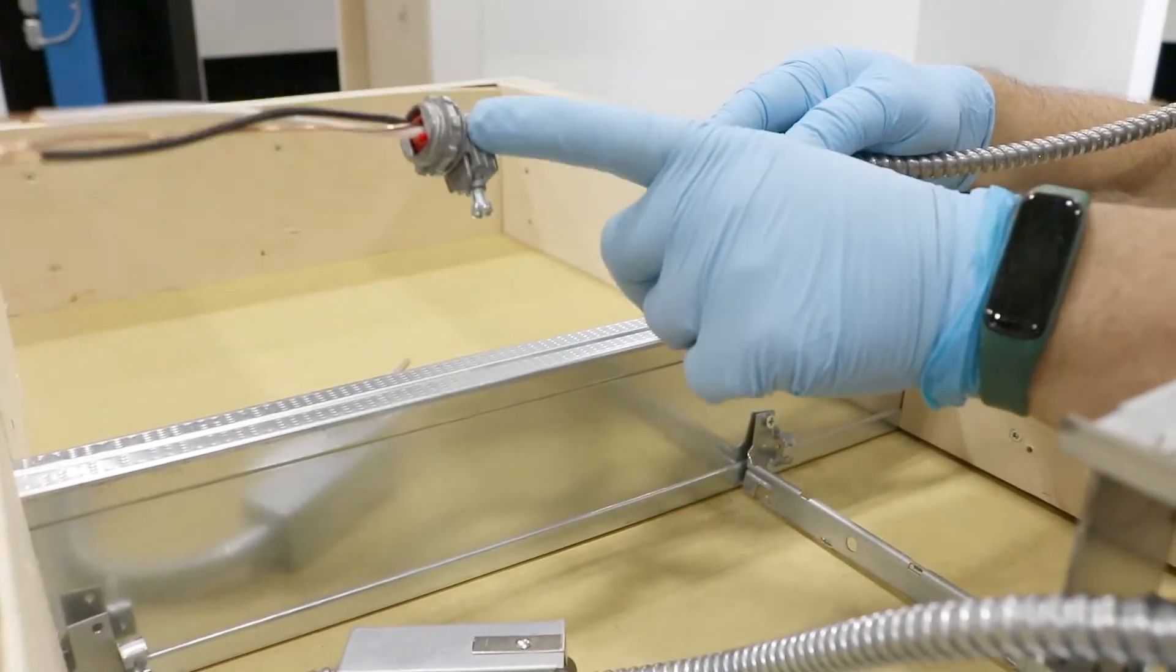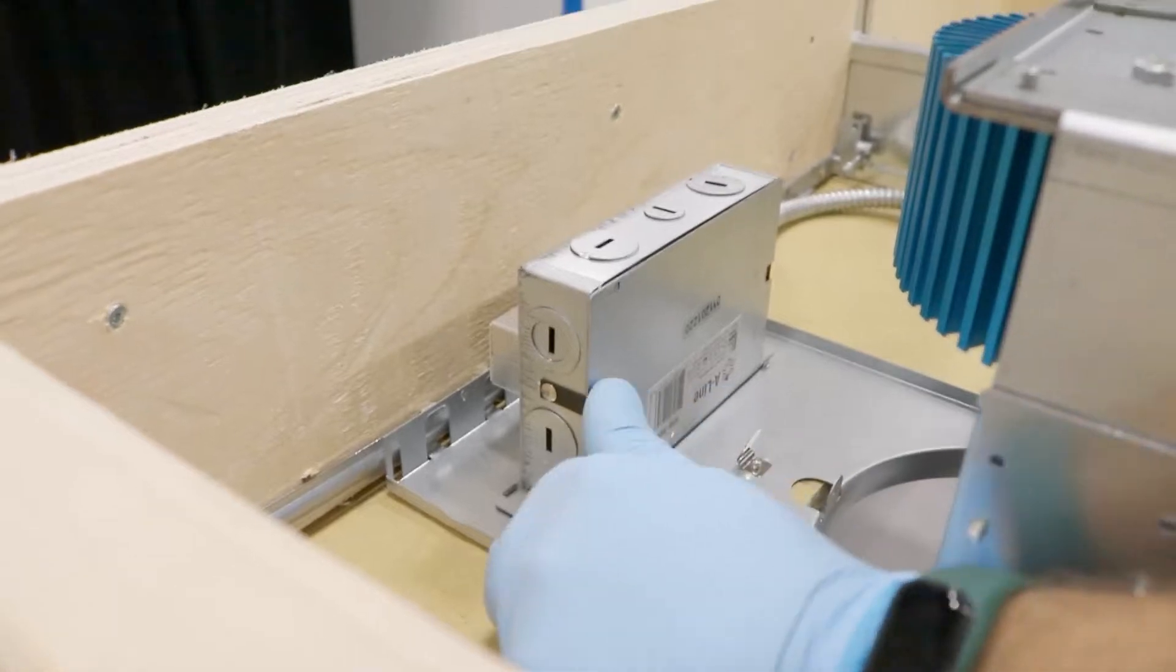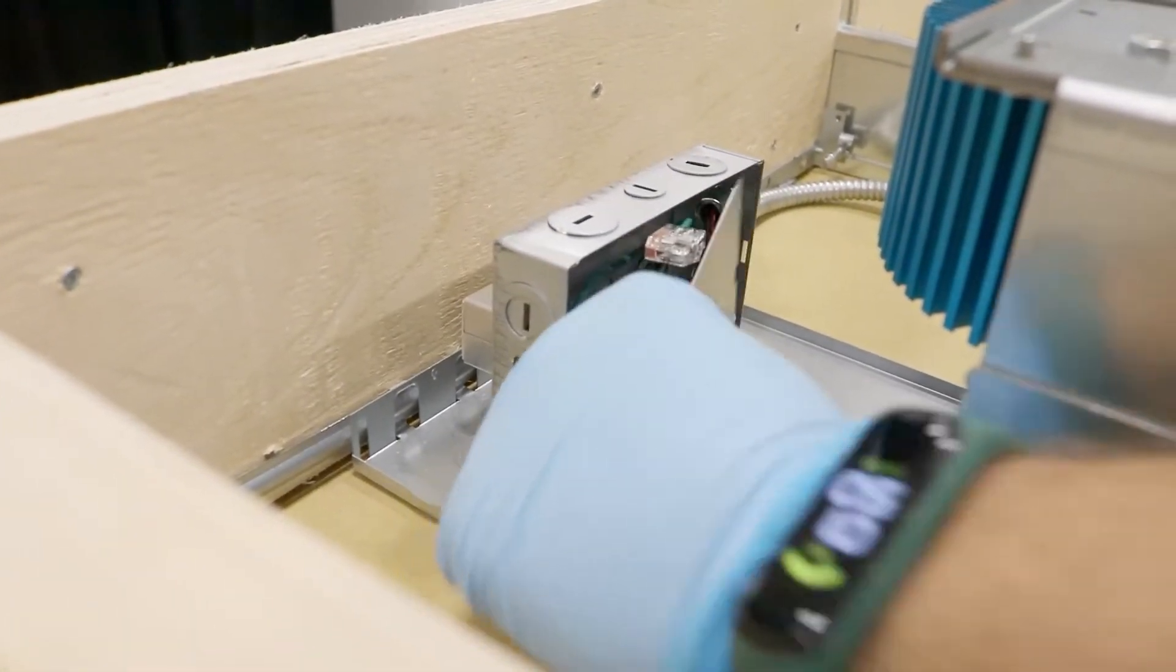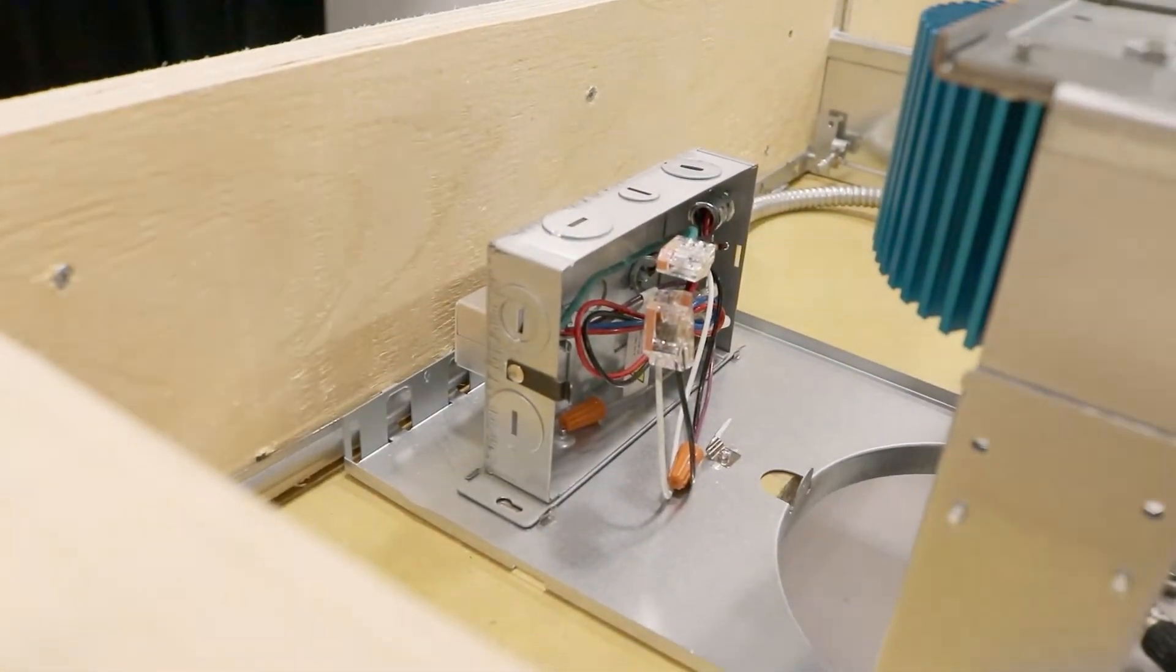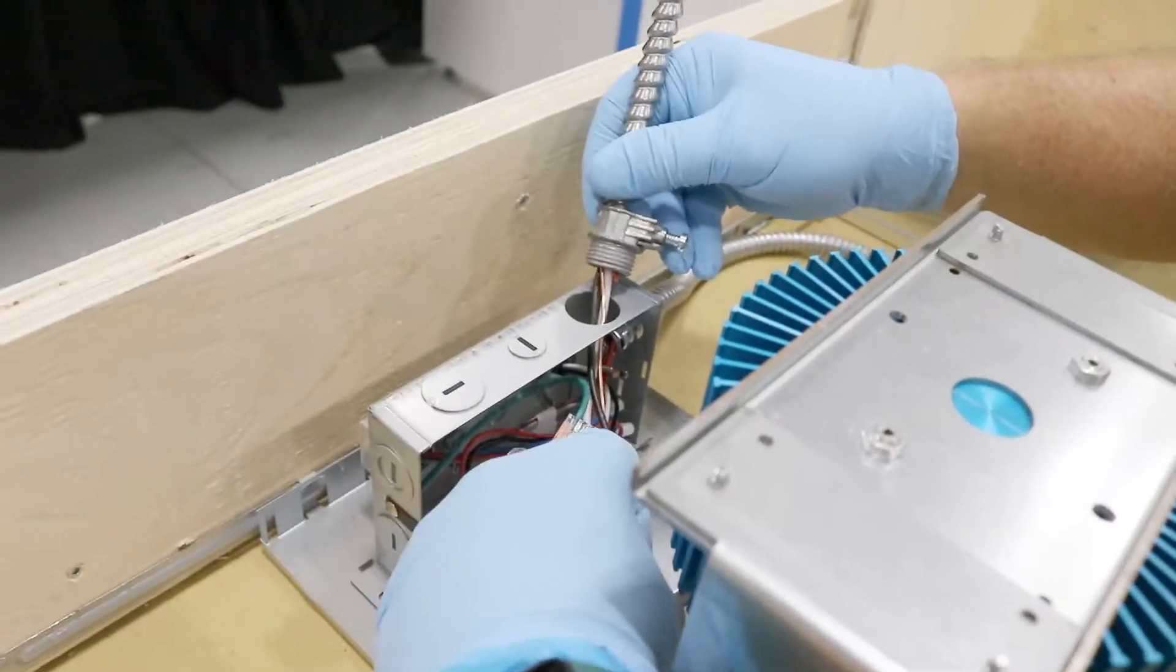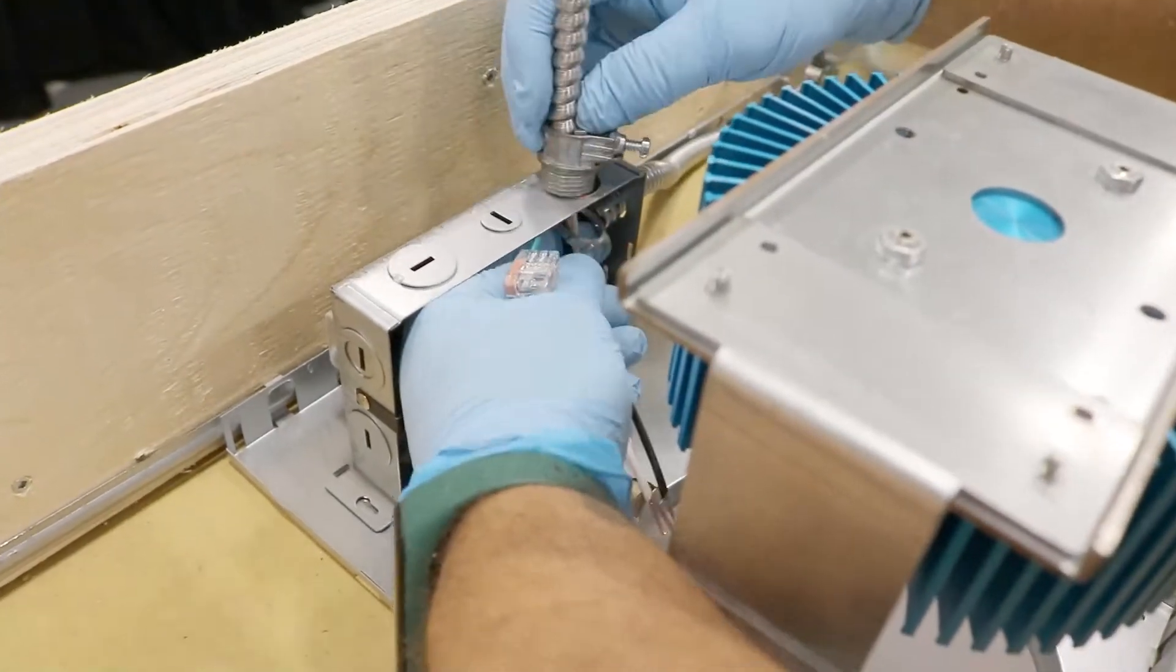Provide electrical service according to your local electrical code for a suitable junction box. Remove the junction box cover and the appropriate knockouts to accommodate the type of electrical service to be used. Insert the electrical supply cable through the knockout in the junction box. Wire the housing using push-in BX connectors.